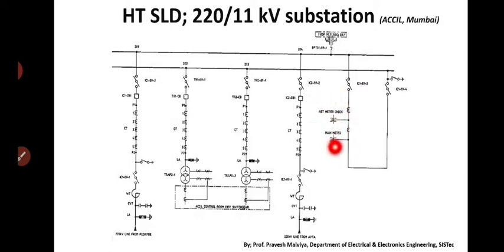Here the amount of power which is consumed by the plant will be measured, and when these two isolator switches are closed, they charge this lower line. When this lower line is charged, it means supply is available here. It transfers its supply to the transformer. So these are the two transformers. Now to protect these transformers, there are two LAs. LA means lightning arresters. The transformer itself is a very expensive unit, so a lightning arrester is essential for its protection.